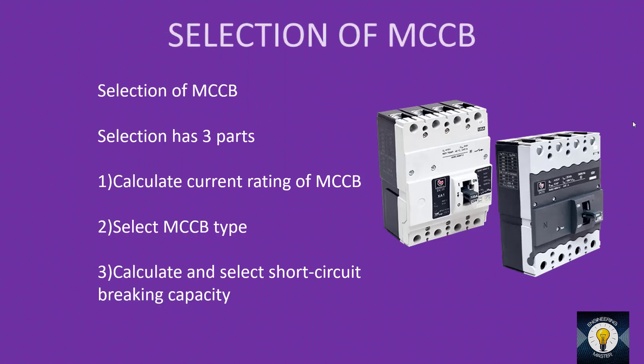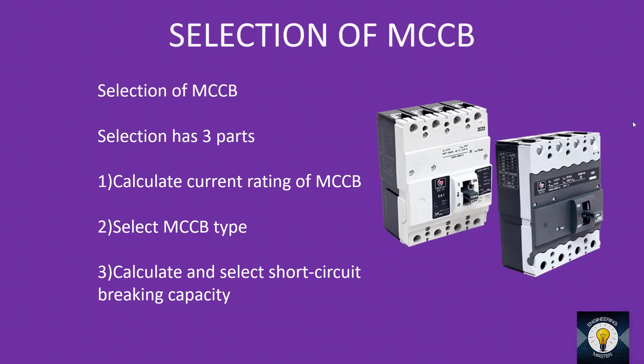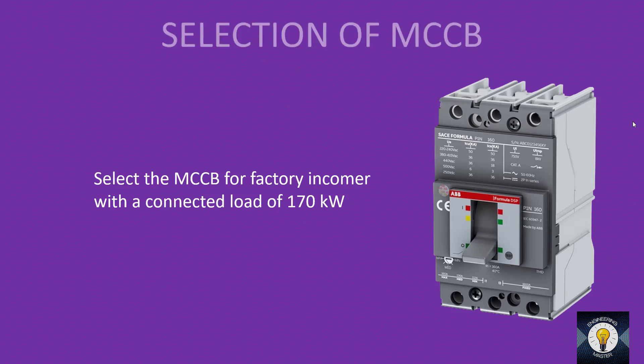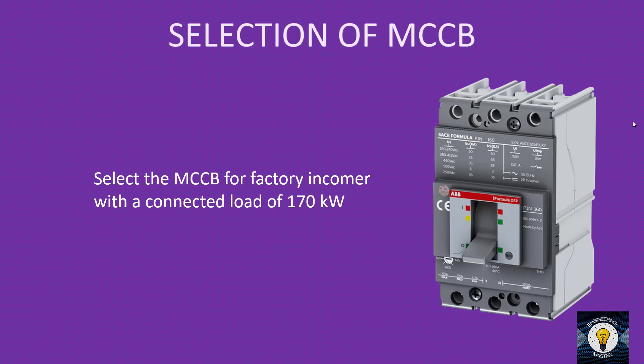How to select an MCCB for your project? MCCB selection has three parts: first, calculation of current rating; second, selection of MCCB type; third, calculation and selection of short circuit breaking capacity. Our scenario is: select the MCCB for a factory incomer with a connected load of 170 kilowatt.